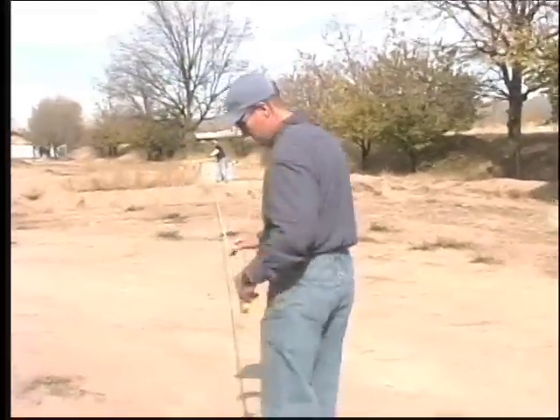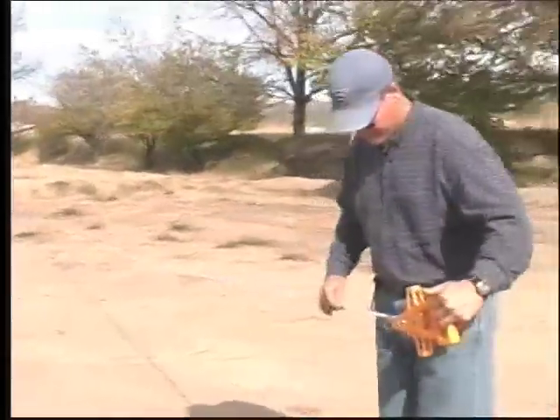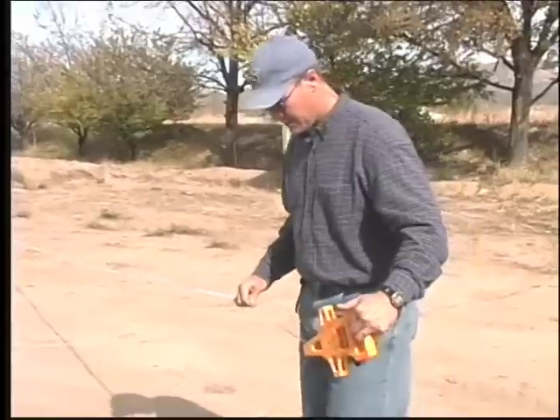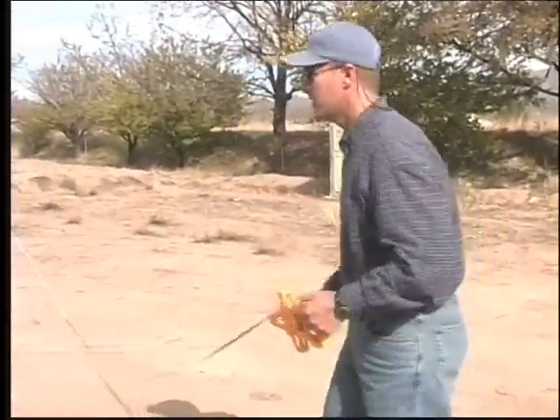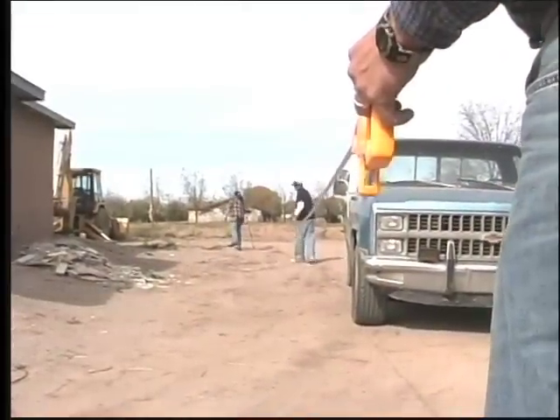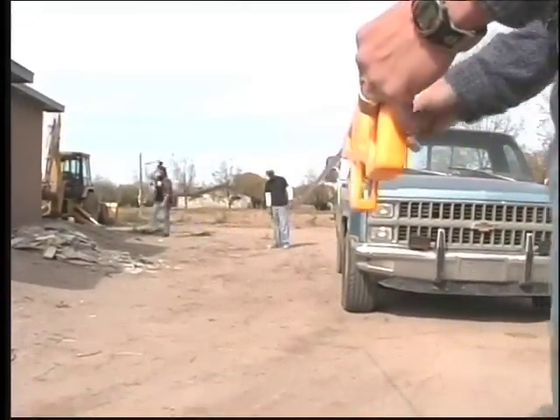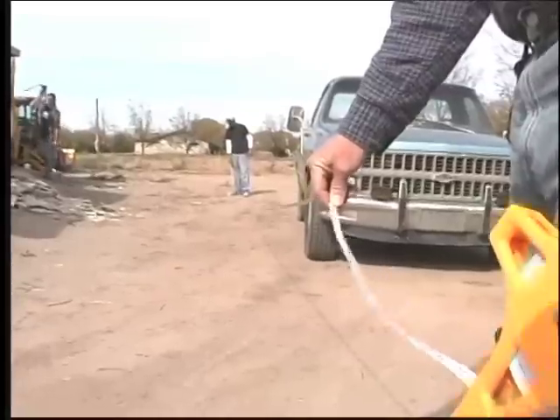The assembly can be performed by one person, and there are no special tools required. But there are a number of cautions. Some manufacturers claim a chamber drain field can be sized smaller than a gravel and pipe drain field. Do not reduce the size or length of the drain field when using the chamber system. This may lead to early drain field failure. The drain field should be sized the same for a gravel and pipe system.